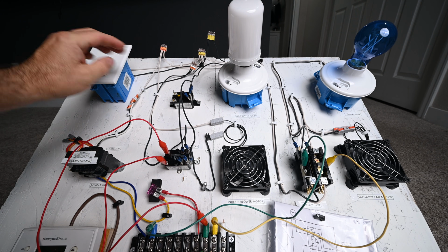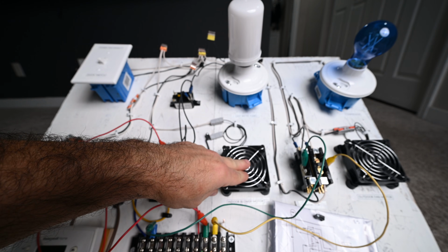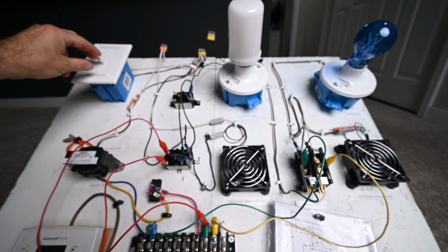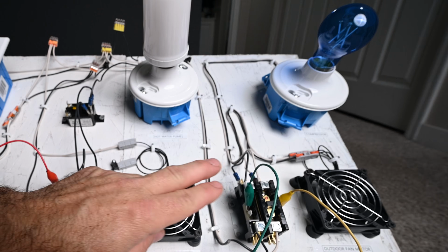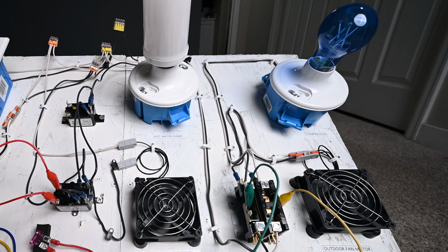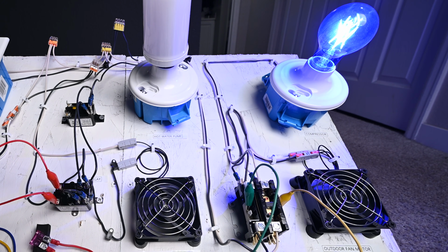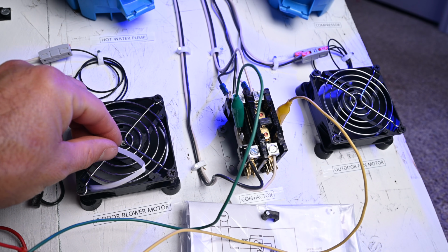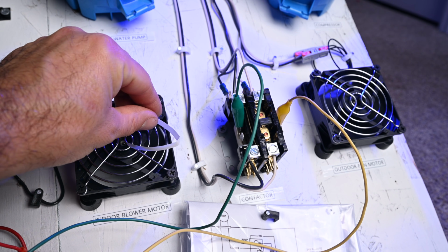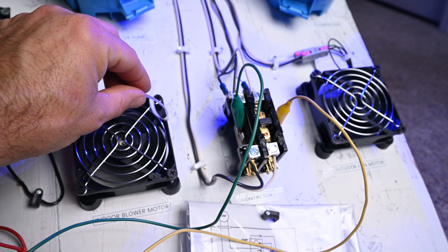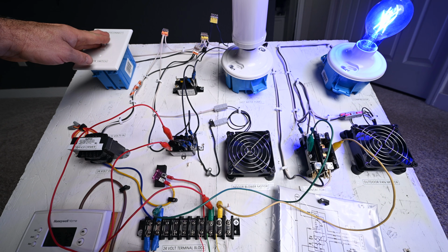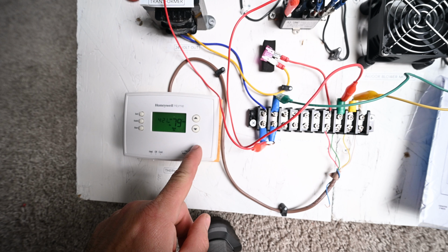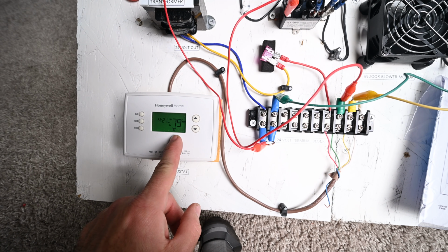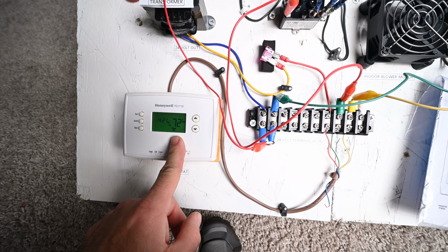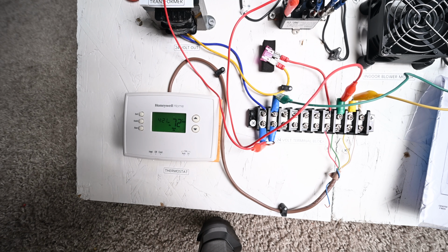Now when I turn the power on, our indoor blower motor should also come on with the condenser, compressor, and the outdoor fan motor. And as you can see, we've got both fan motors now running. Going to turn off the power, and I'm going to check the heat. I've got my thermostat set to heat. Heat's on. There's no time delay on this, so once we hook up the heat, it should come on if we hook it up right.